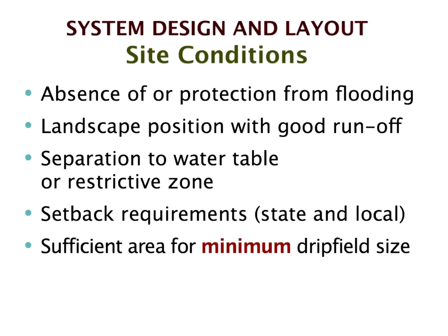Separation to the water table or any other restrictive zone. Obviously, we often have rock and clay layers or other impermeable layers, or layers in which the perk rate is lower than the upper layers. Setback requirements, state and local, and the sufficient area for the minimum drain field size. If you get a design that comes in with the minimum drain field size, that just happens to exactly fit the area available.